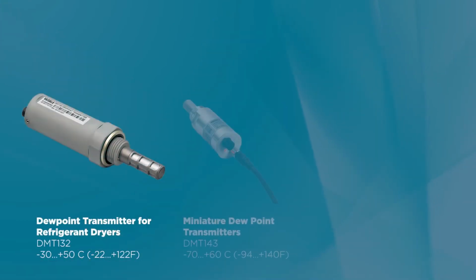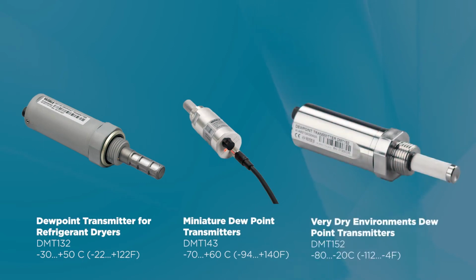Let's say you're looking to measure dew point in a compressed air system. Our DMT-132, DMT-143, and DMT-152 compact dew point transmitters are each appropriate for permanent installation to different compressed air systems. The DMT-132 is specifically designed for refrigerant dryer systems. Our DMT-143 is perfect for most desiccant dryer systems. And our DMT-152 is the most sensitive, providing a solution for systems meeting an air quality Class 1 standard, thanks to its calibrated measuring range down to -80°C dew point.